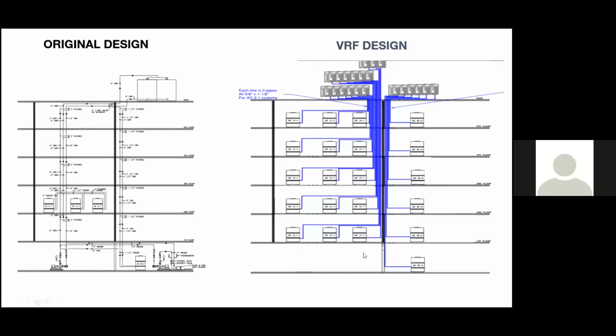So with us breaking up the 21 systems into those different risers as well, we could just install those systems for each tenant to avoid disrupting the entire building all at once. And then just talking about the alternative VRF on the right here, with each piping shown from the condensing units on the roof down to each air handler. So as I mentioned, each air handler would have a dedicated 2 pipes from 1 condensing unit.